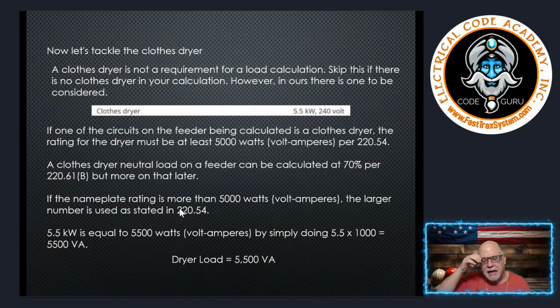All right, next, let's tackle the dryer. This is easy peasy, okay? So if you go look in the NEC, now, I want to remind you, you are not required to add a dryer circuit in a dwelling. I know that might blow people's minds. They're like, well, every house I've ever done has a dryer. Yeah, and you're going to account for it if it has a dryer. But there's absolutely nothing that requires it.